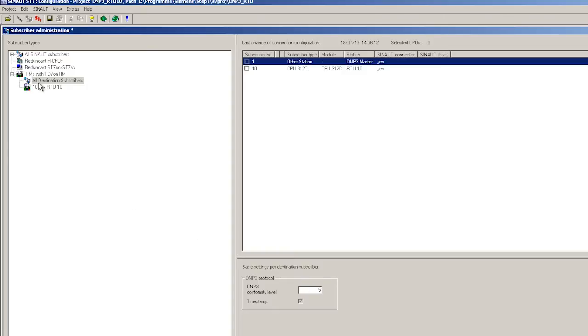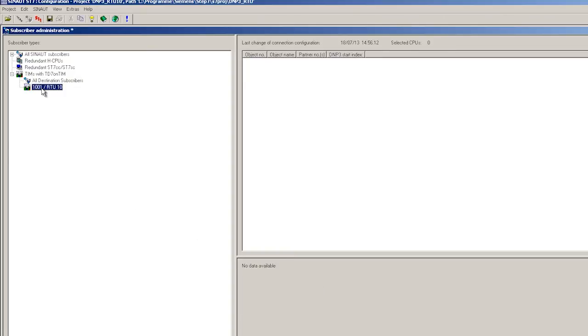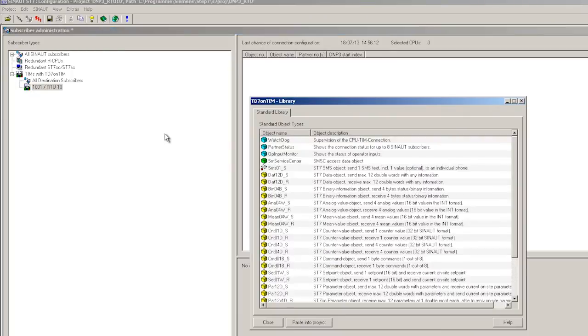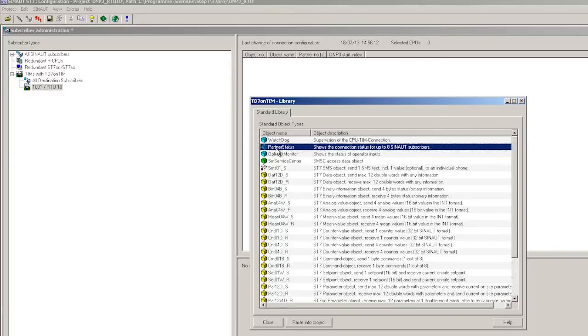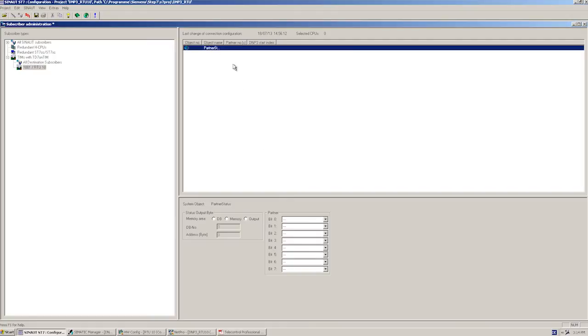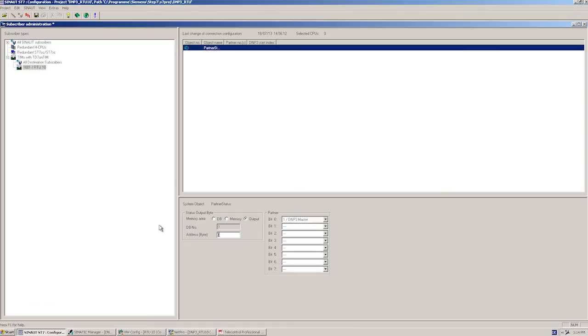Finally, we begin configuring the data point objects by selecting the TIM and opening the td7 on TIM library. It is recommended that you set up the partner status as basic setting. The partner status indicates the connection status between RTU and master. To display the status information on the CPU, here we select, for example, output byte 124.